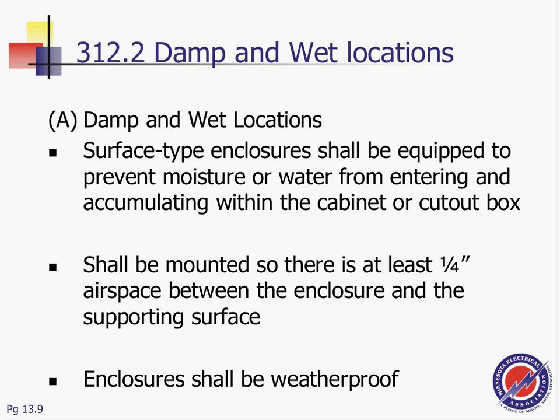Let's go into 312. So here we go, 312. We're getting into a couple of things. The damp and wet location. If you are to install in a damp and wet location, the surface type enclosure shall be equipped to prevent moisture or water from entering and accumulating within the cabinet or the box. So in a wet location, it's going to be designed in a way where you don't have moisture dripping right into your equipment.